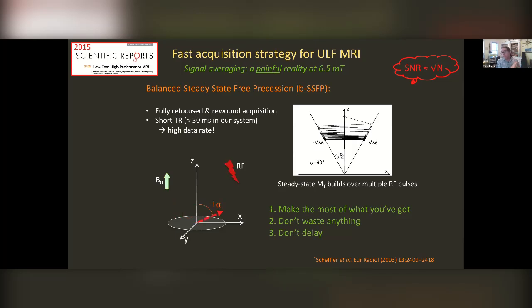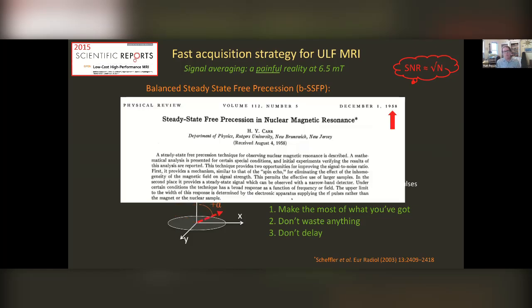And so this gets us to the rules of low field magnetic resonance, which is, when you have low SNR, make the most of what you have. So large tip angles, sample all your magnetization, don't waste anything. So typically crushing is a bad idea, and don't delay, right? If you have long dead times, you're not taking data. Of course, Herman Carr knew this in 1958 when he wrote down SSFP.